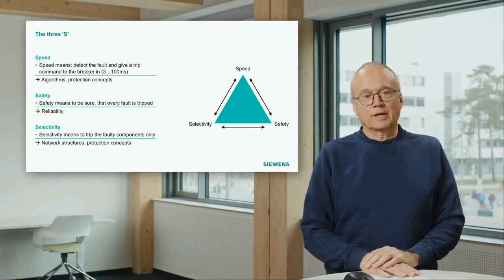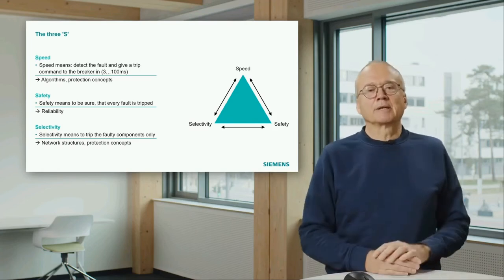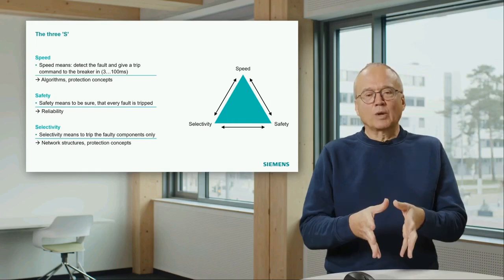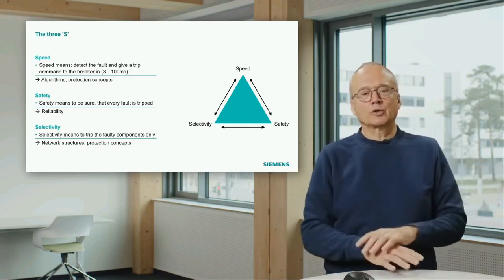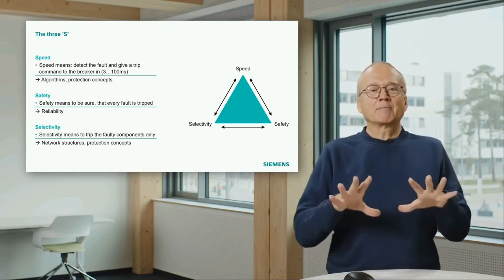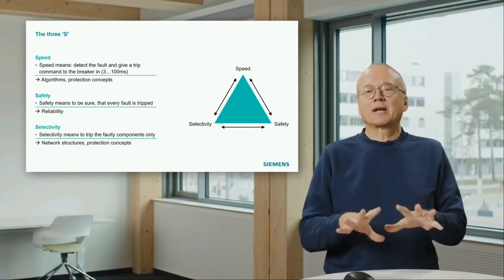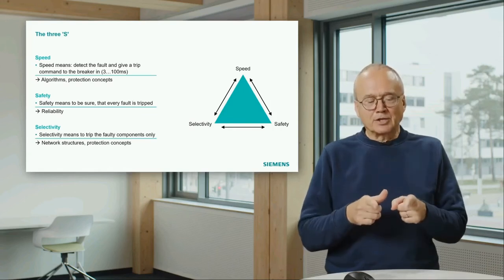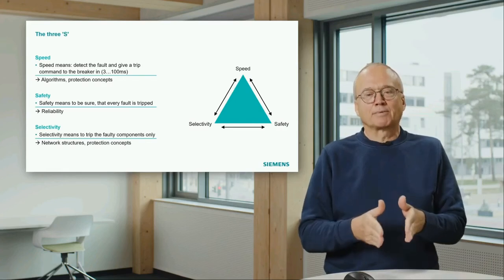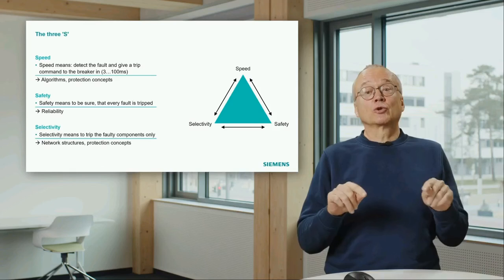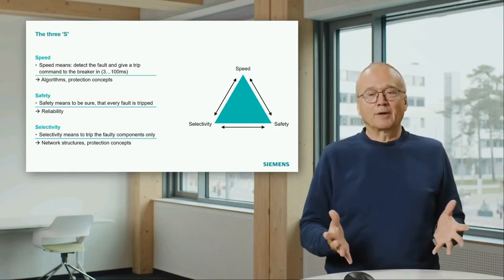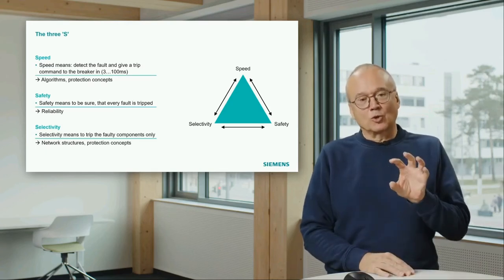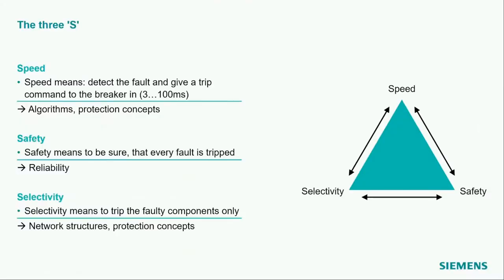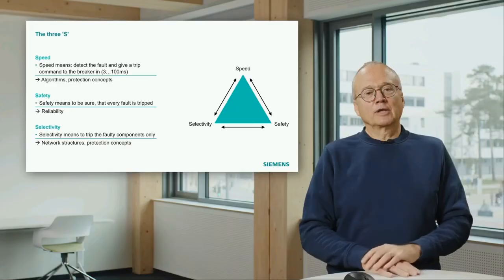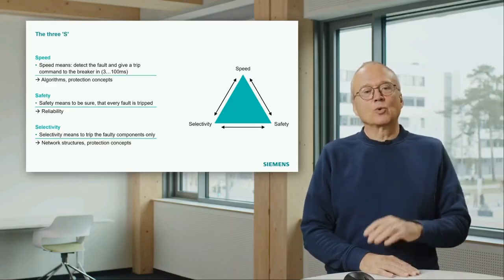And the last issue, which also has to be mentioned, is the selectivity. What does selectivity mean? Selectivity means if you have a short circuit somewhere in the network, there is short circuit current coming through different lines, cables and transformers. That means several devices in the system will see there is something wrong. But only the protection device of the faulty line or cable has to trip. The other ones see the fault, but they should not trip, because we don't want to trip 5 lines if there's a short circuit on one line. And this thing is called selectivity, that only the faulty component is disconnected from the rest. And that is a very important issue, and we will have several chapters dealing with what we can do to get selectivity.